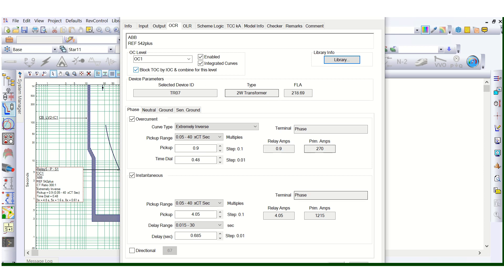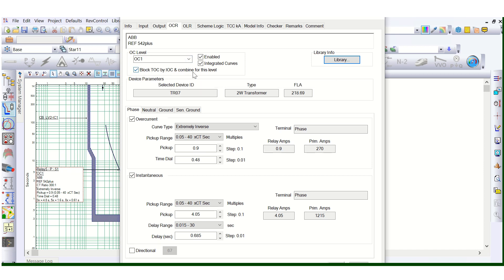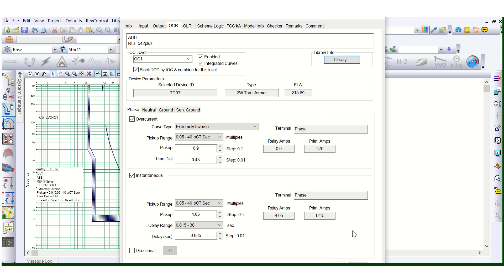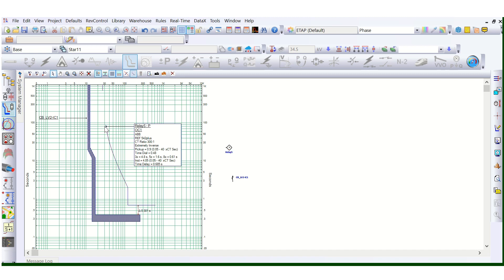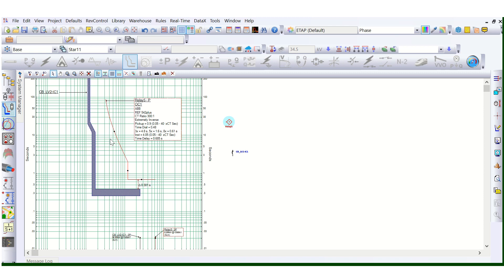Block TOC by IOC is very simple to apply in ETAP software, but in the actual field OEM support is required. The relay manufacturer can only make certain modifications — they need to wire the logic inside the relay so that this feature can be enabled, meaning block TOC by IOC. A site engineer or commissioning engineer cannot do this work — only OEM support is required for this particular activity. Like this, the coordination is now achieved with the combination of 51 and 50.